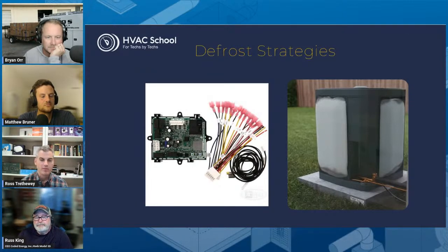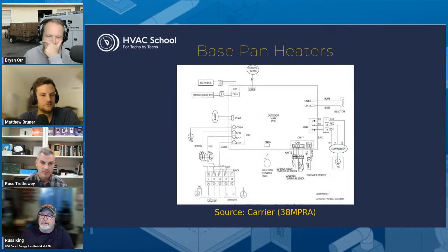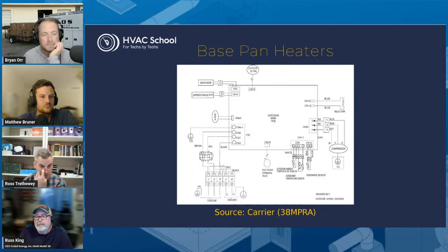Yeah, the other thing to add with defrost is about base pan heaters. So that's a big difference between a cold climate heat pump and, let's say, a standard heat pump. Yeah. And so, for anyone, I don't know if everyone knows what that is. I don't know if you want to explain what it is, but please do, for people who aren't used to it. Yeah. So these cold climate heat pumps, one of the things that differentiates them from a standard heat pump is that when it does go into defrost, it's obviously switching to cooling mode for that time. And so it's actually extracting heat back from the building and sending it back to the outdoor coil, warming up that coil and trying to melt that ice.